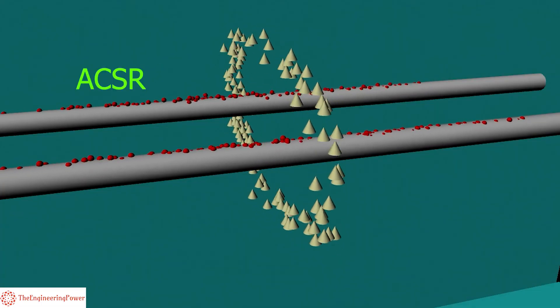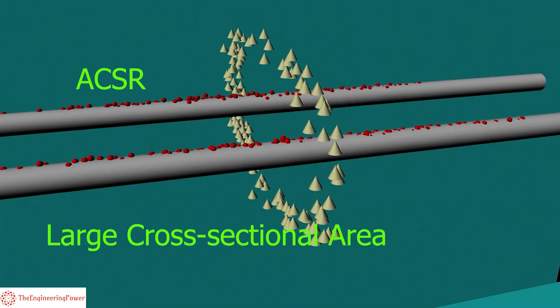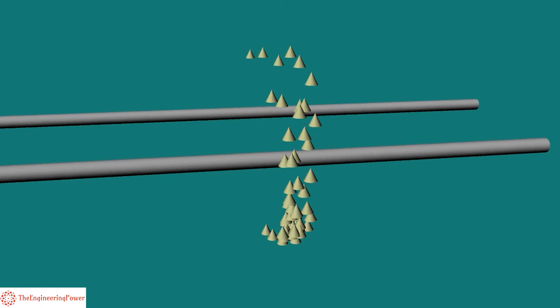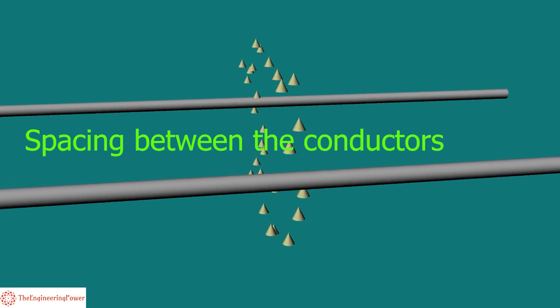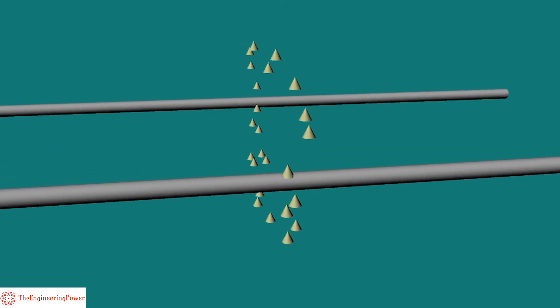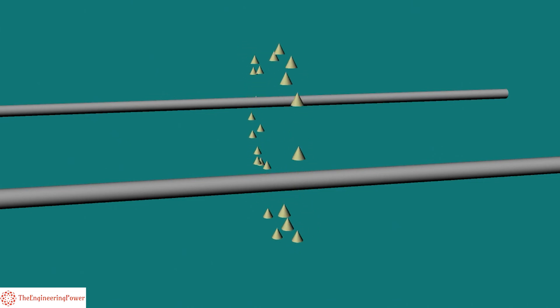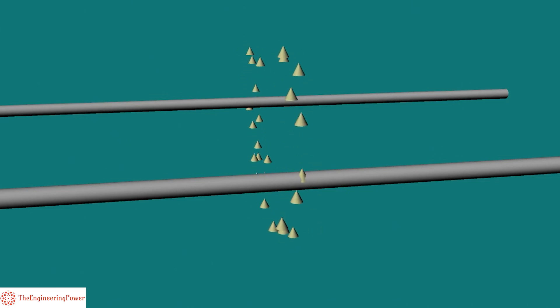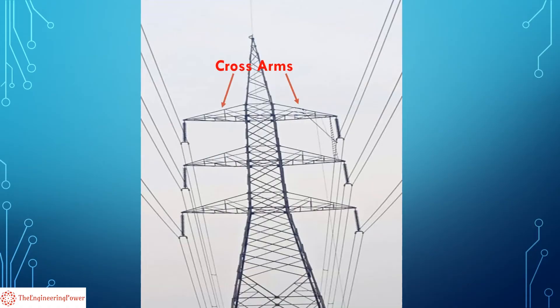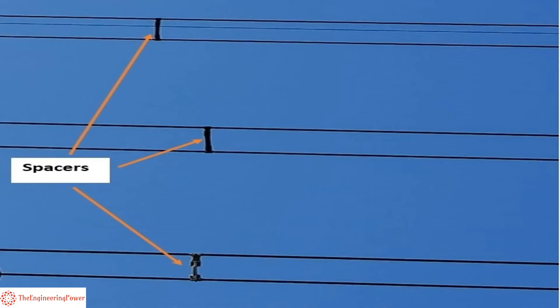The next method is by increasing conductor spacing. Corona loss can be minimized by increasing the spacing between the conductors. However, we can increase the distance between conductors only to a certain limit, because the cost of supporting structures — that is, cross arms and other hardware including spacers — will increase considerably.